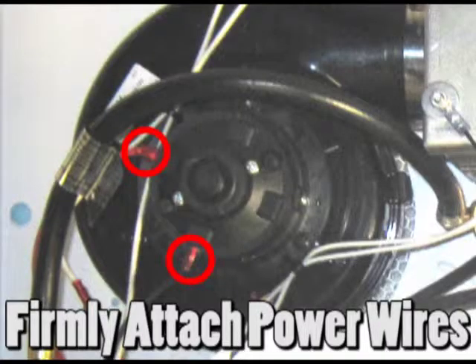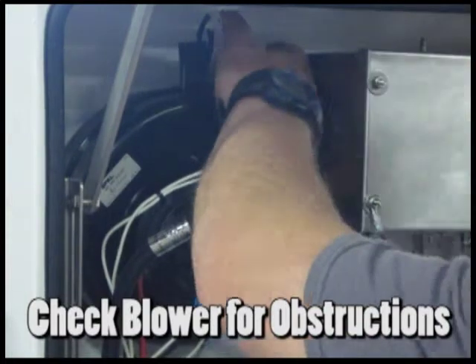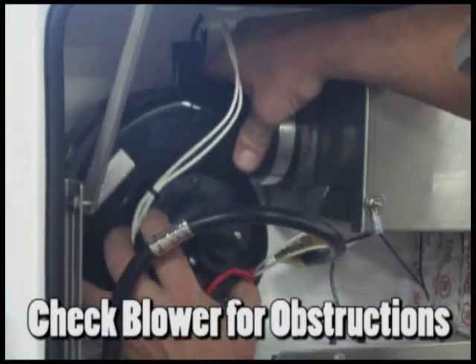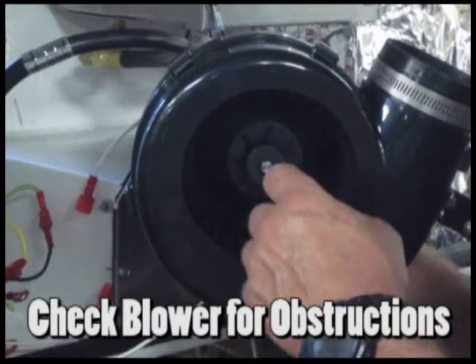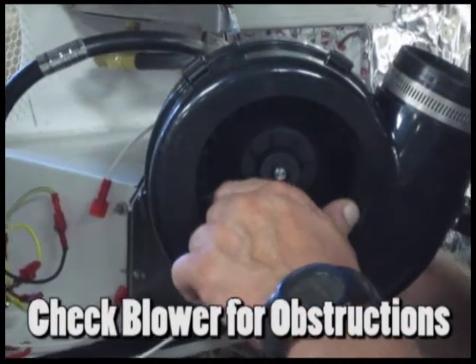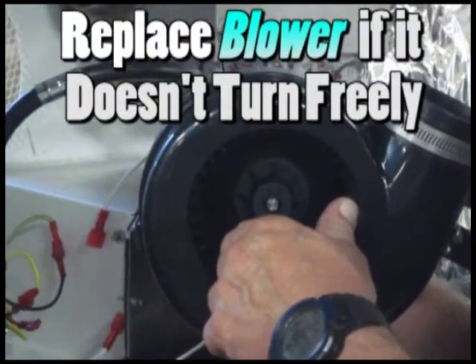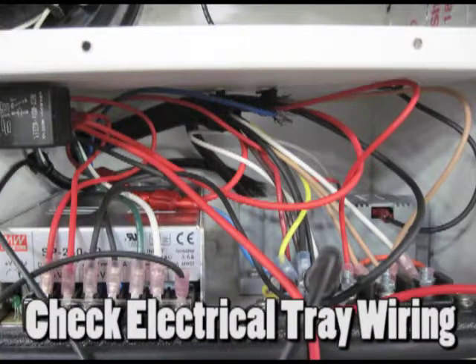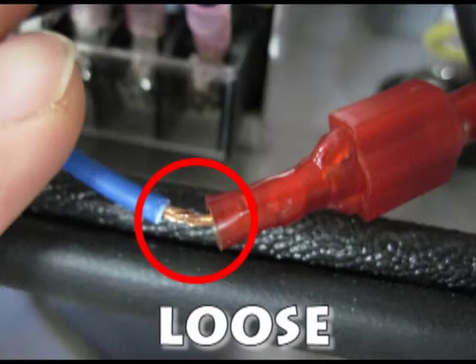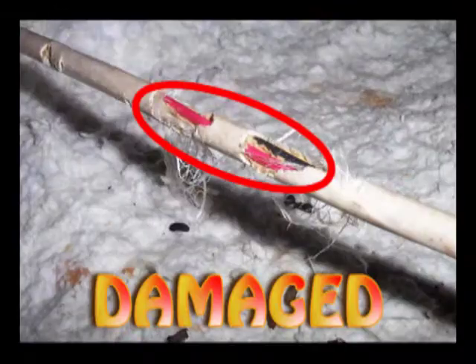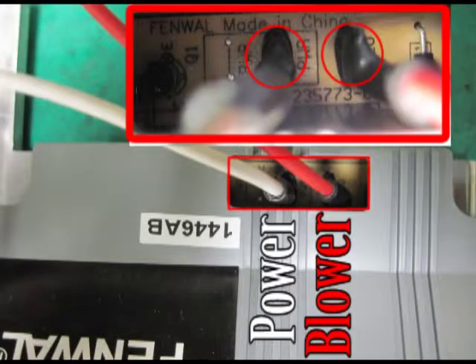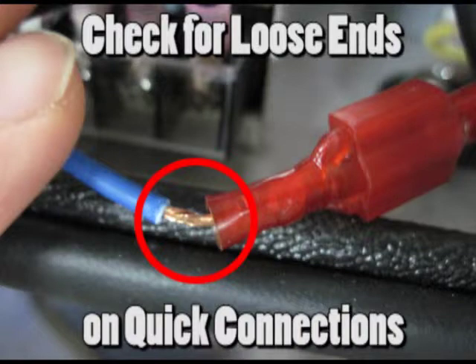Check that the 2 wires to the blower are firmly attached and there are no obstructions in the blower. To check for obstructions, loosen the hose clamp on the blower and slide it off the combustion chamber. If there are no obstructions, the blower should turn freely. If the blower does not turn freely, it needs to be replaced. Check the wiring connected to the electrical tray. Look for loose, corroded, or damaged wiring, especially at the power and fan terminals on the back of the ignition module, as well as loose ends of quick connections.